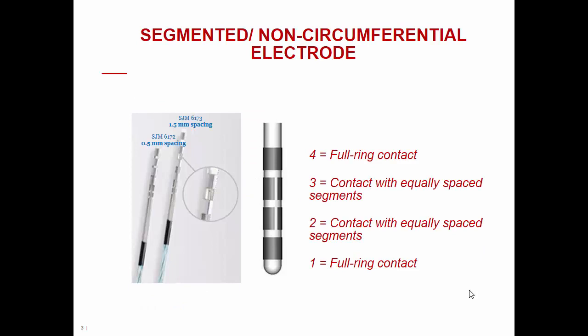In order to understand the functionality of Informity, we need to introduce a couple of key critical concepts. The first one is the anatomy of the DBS directional lead. The DBS directional lead consists of four different levels of stimulation, of which level 1 and level 4 — the most ventral and the most dorsal — are full ring contacts, while the two intermediate levels, level 2 and level 3, are further divided into three equally spaced segments or electrodes that allow directional stimulation.